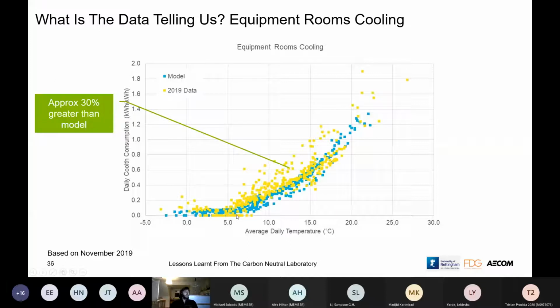Now, these yellow dots are what we've measured from the actual recorded data on site, and it's remarkably well matching the model. Our cooling demand is still about 30% higher than the model, and again, I think this is down to controls, which is increasingly appearing to be one of the biggest energy consumers. It's not necessarily bad controls, but controls can never be perfect. They can never exactly match the demand. So however much we try, we're always going to overshoot and undershoot in terms of heating and cooling, and that just adds a little bit of extra energy consumption.